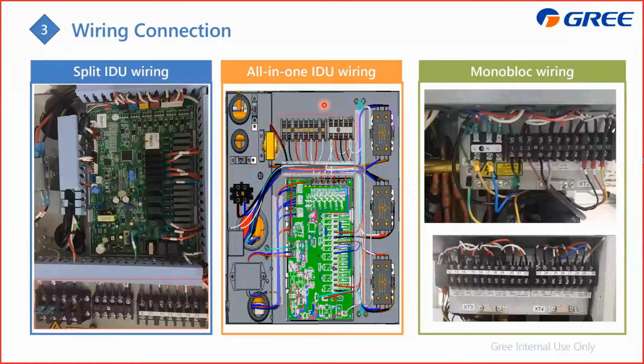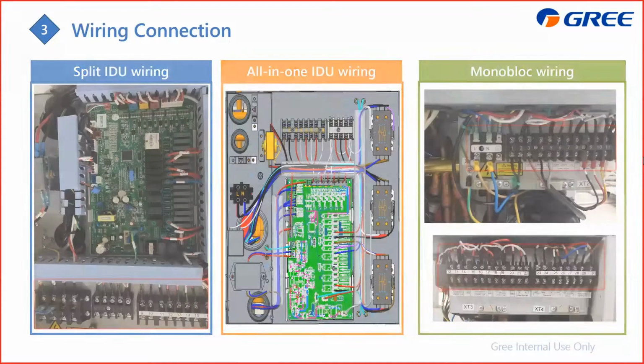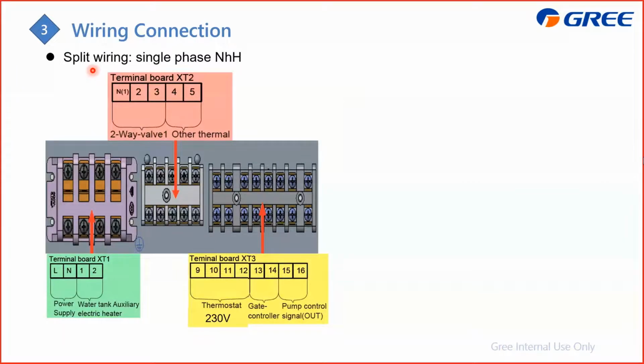As for the monoblock, it is the most complicated because you need to connect many wires, divided into two parts. For the split type, this is the power supply, LN for the single-phase supply, and 1, 2 is for the water tank heater. XT2 is for the control of the two-way valve and another thermal. XT3 is for the thermostat, connected here, and gate control. And if you need another water pump, just connect the control signal here.